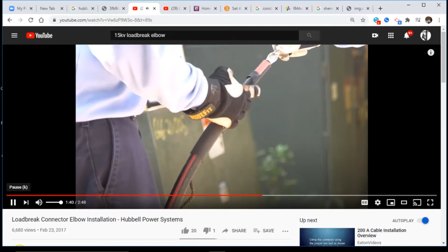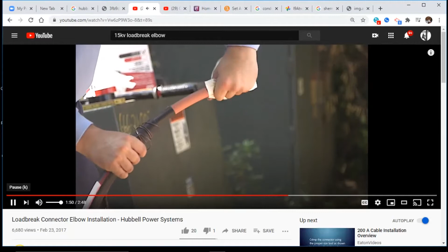And remove cable insulation shield, cut squarely, making sure not to nick the insulation. Bevel the insulation end 1/8 of an inch. Refer to the seal kit instructions if the seal kit is used. Clean and lubricate the cable insulation and cable entrance to the elbow, making sure that each are free from contaminants. Use the supplied lubricant, as other lubricants can be harmful to products. Slide the elbow onto the cable using a back and forth twisting motion.